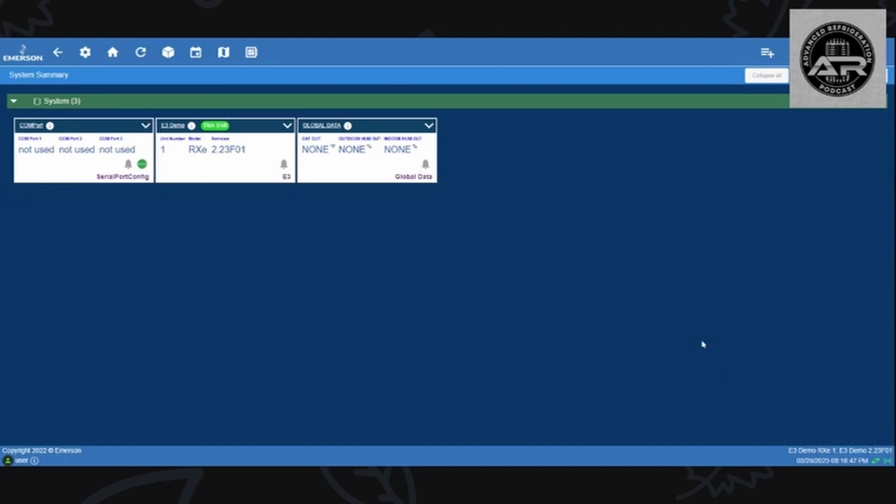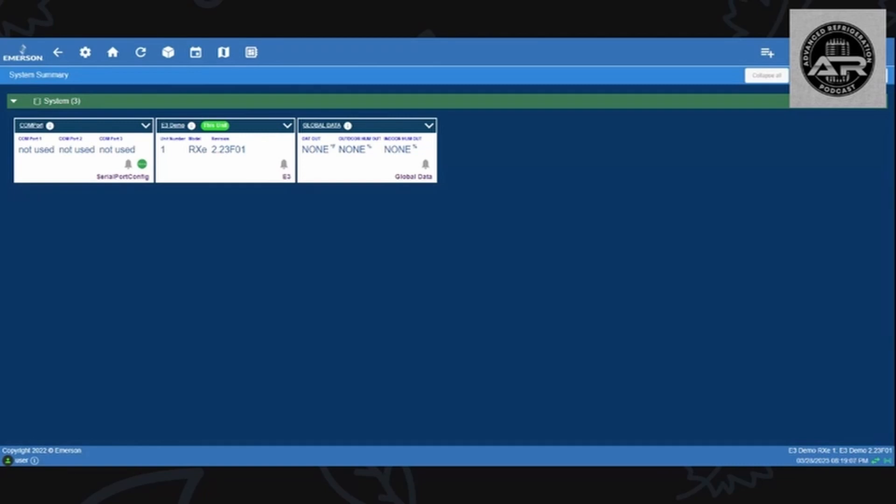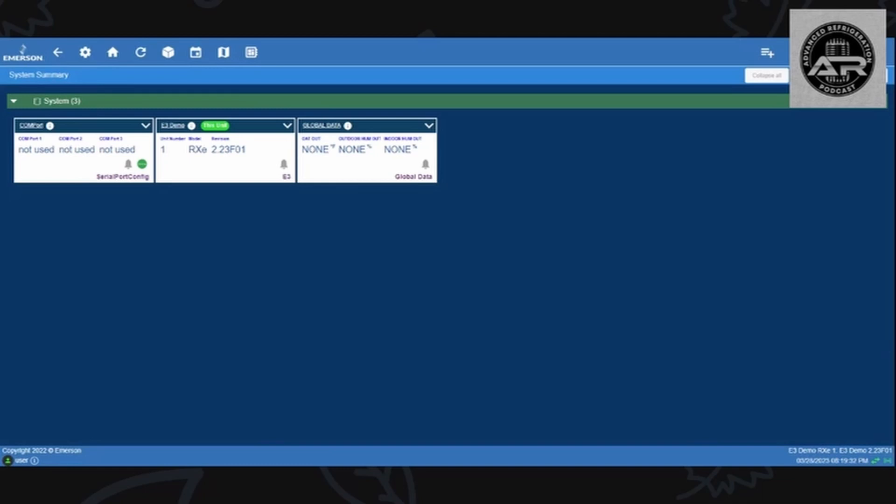For the E2s on the refrigeration side we used to have RX-300 and RX-400. For the E3s the equivalent of a 300 is an RX, the equivalent of a 400 is an RXE. That same model structure follows for BX and CX. There's also a SF which is a small format model, same hardware but less applications. If you have a C-store or something and don't need a lot of applications, there's no reason to buy an RXE. If you had a rack like some of these smaller convenience stores have a rack, you'd probably want a CX or CXE if you have HVAC, lighting and refrigeration.